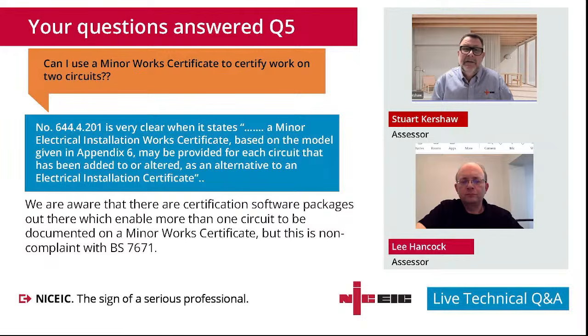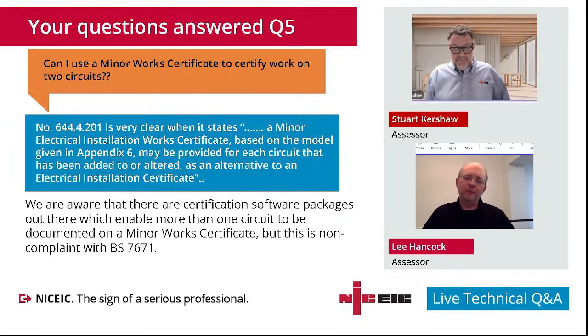So it's quite clear, as far as I'm concerned, that the details that you're recording on that minor works are relevant to that circuit that's been altered or extended or added to. So as much as it can be inconvenient to contractors for certain scenarios of work, multiple repairs in one building, this is a situation where I was questioned about the multiple minor works, and I said I don't believe it's compliant to 7671, convenient or not, because the information recorded on that's too blanketed, and there's various works carried out from various DBs. It's very clear, really, each circuit that has been added or altered. So no, the answer is it's a minor works for each alteration or addition for each circuit that's been worked on. It actually states on the certificate itself, doesn't it, like the notes for recipient, what it's supposed to be used for.